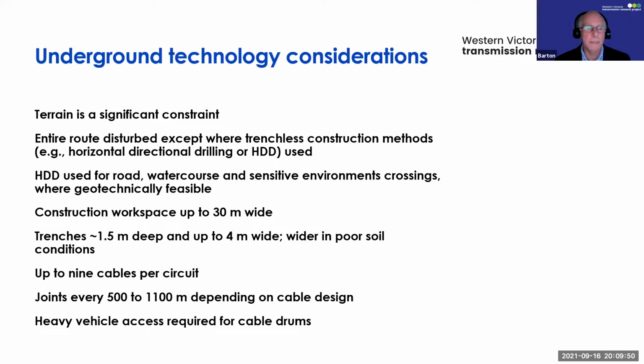And the reason for that is that HVDC cables are heavier, with a much bigger cross-sectional area because one cable carries all of the current and the other the return current. So we still end up with about 500 to 1100 metres per drum. That doesn't change, and we still need heavy vehicle access. So the key difference is ultimately the width of the easement. In terms of construction and constructability issues, they're very similar for both.